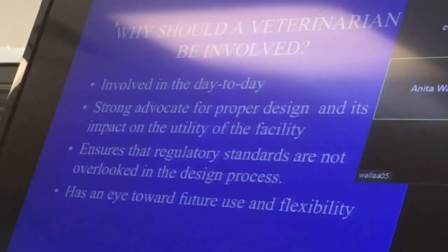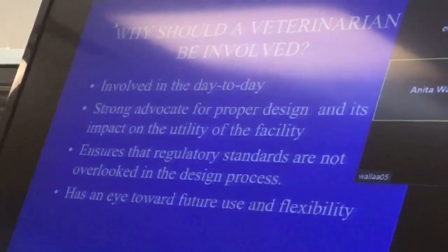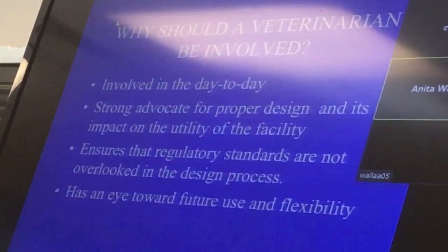On the surface, that sounds like a reasonable compromise, cost-saving and more energy efficient. But you as a veterinarian would say, well, what happens if I lose power or something happens to my ventilated cage? Now my animals are in a room that has an air exchange rate of 5 to 7 air changes per hour, which is unacceptable.